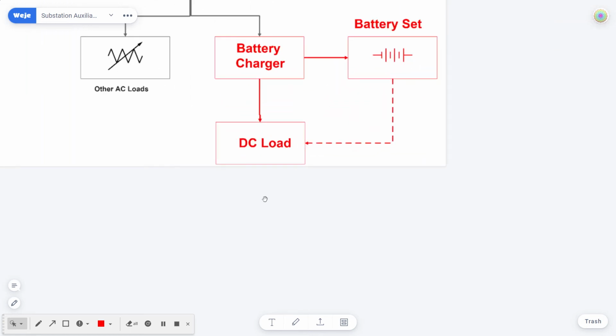Now, what are the DC loads in the substation? DC loads are the essential loads in the substation. Essential loads like relays, meters, energizing the tripping and closing coils of the circuit breakers, then DC emergency lighting in the control room.